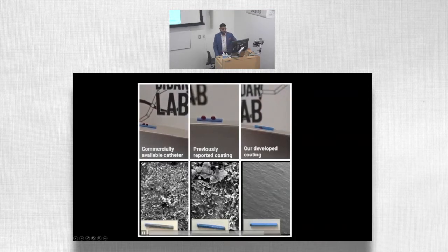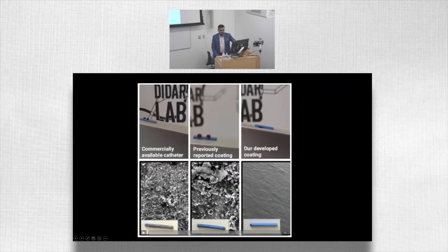If you look below at the electron micrographs, this is basically thrombus on the surface, and you see that the omniphobic coating doesn't modify the surface, and no clot sticks to it. This coating is moving along very nicely and is coming along to commercialization. You can imagine setting up an ECMO circuit or a bypass circuit not needing heparin if nothing's going to stick to it.